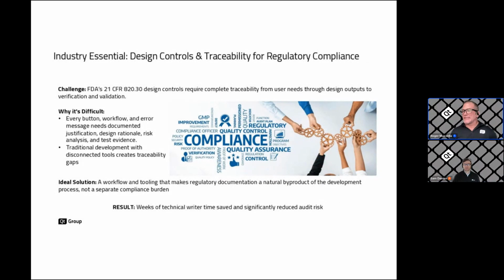Yeah, fantastic. All right, so we've got a couple more slides, then we're going to wrap up. So obviously, design control traceability. We mentioned this. You mentioned this in the beginning. I knew we were going to come back to this slide, Sam. So design controls, traceability for regulatory compliance. Everything needs to be completely traceable, from user needs to design inputs to the verification and validation. And obviously, the FDA 21 CFR 820 calls that out. So every button, workflow, error message needs to be documented, justified, rationalized, right? And sometimes traditional development with those disconnected tools create those traceability gaps. I know that in the beginning of my career, I was a QA engineer working on patient monitors, and boy, the paperwork we had to do to have that traceability way back then, and now I know it's even more. Comments on traceability, Sam?